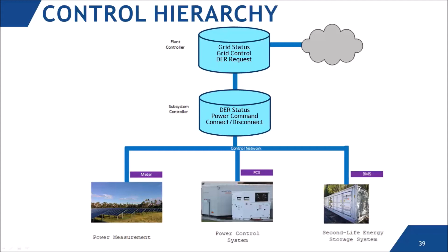If you go down into the energy management layer, it's more about DER status - what is the status of the DER, creating some power commands for the DER, and connecting and disconnecting the DER as needed. And then at the bottom levels, at the meter, PCS, and the BMS, they each have their own sets of data: the power measurement for the meters, the power status and command for the PCS, and for the BMS it's really the current limits, SOC connection, but other things like current and voltage are also available.